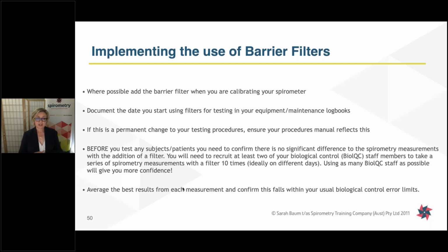Before you test any subjects, it's a good idea to make sure there's no difference in measurements with the addition of a barrier filter. So you'd use maybe a couple of staff, you'd measure yourselves 10 times with a filter, 10 times without a filter, and take the average of each of those 10 results, making sure those averages are not too different. And using those averages as well to check with your usual biological control error limits, if that's something you're already doing in your service. Where possible, it's really recommended that you add the barrier filter when you're calibrating your spirometer as well.